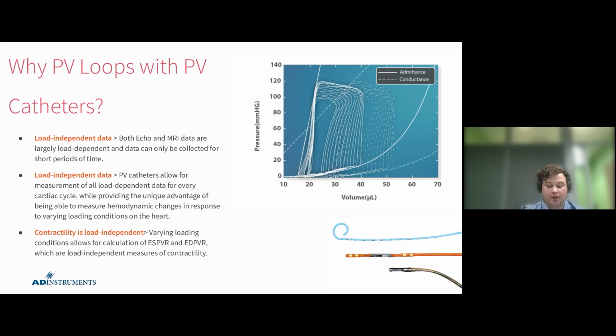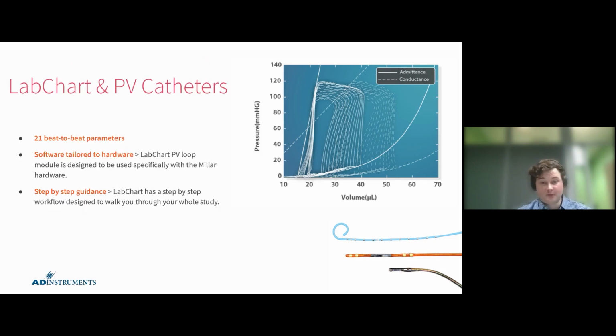The reason this is important is because contractility, the myocardium's intrinsic ability to contract as a muscle, is a load-independent parameter. With the varying loading conditions of a PV loop study with a PV catheter, you're able to calculate end systolic pressure volume relationships and end diastolic pressure volume relationships, which allow you to obtain those other load-independent parameters of contractility. And you're able to do this all while using the PowerLab and LabChart system, which gives you 21 beat-to-beat parameters, software that is tailored to the specific hardware you're using, and a step-by-step workflow to set up, calibrate, and complete your study.